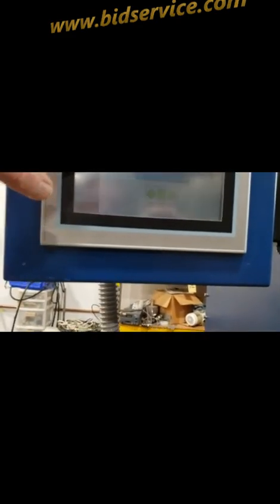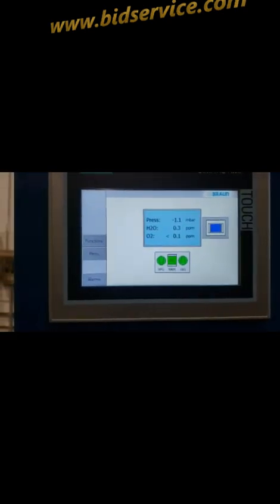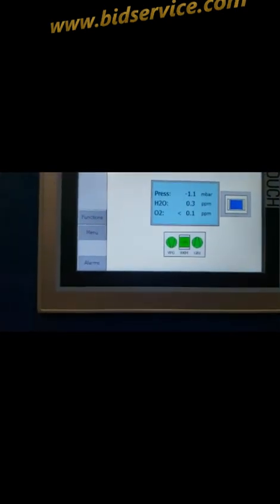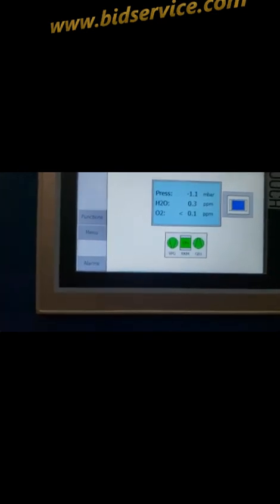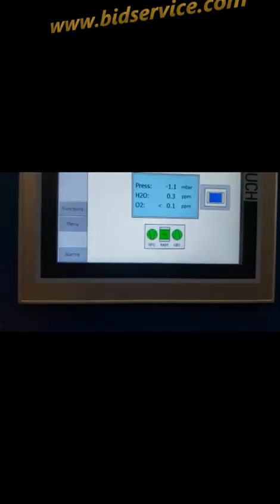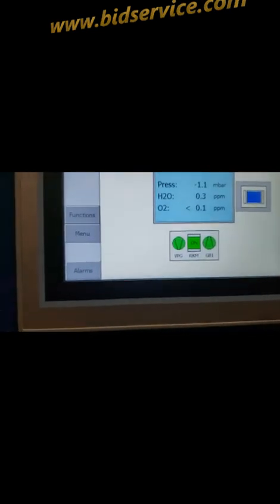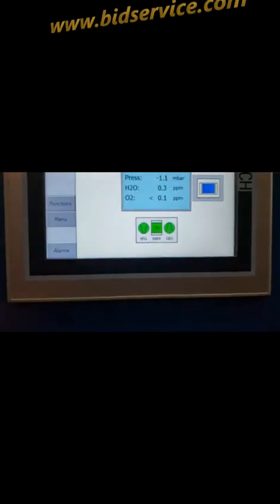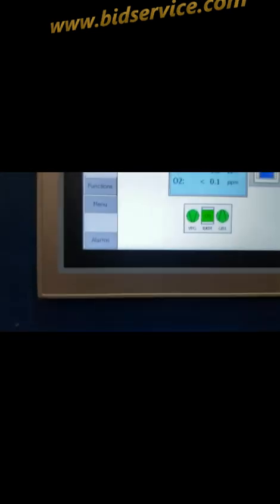And then here's your operator panel, your Siemens HMI. It's timed at, I think, about 20-30 minutes, it'll go ahead and darken out as a screensaver, so we'll just go ahead and hit that. So you can see the pressure set right now at minus 1.1 millibar. And as you can see, the H2O inside the box is 0.3 parts per million, and the oxygen is less than 0.1 part per million.